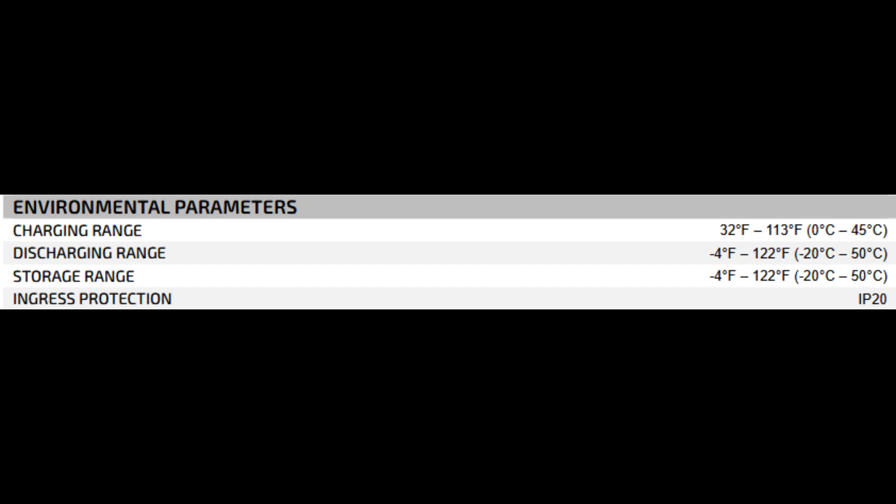Environmental parameters: charging range 32 degrees Fahrenheit to 113 degrees Fahrenheit. Discharging range minus 4 degrees Fahrenheit to 122 degrees Fahrenheit. Storage range minus 4 degrees Fahrenheit to 122 degrees Fahrenheit. Ingress protection IP20. You should only charge these above 32 degrees Fahrenheit. Charging lithium batteries below freezing can damage them. IP20 means they're not waterproof. They're intended for indoor, protected environments like a server rack or battery shed.